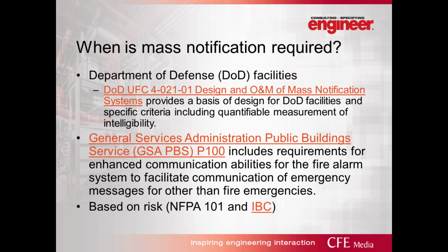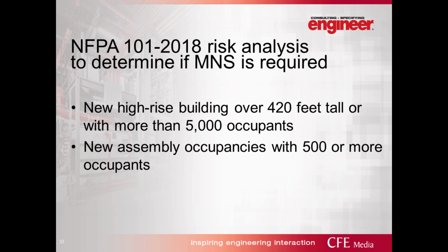I'm going to skip to mass notification. When's it required? The Department of Defense is the only organization that actually, at this point, mandates a mass notification system, and they have a standard in the UFCs. It's DOD UFC 4021-01, which provides the design guidelines for mass notification systems. Now, the General Service Administration in PBS P100 does include requirements for the fire alarm system to provide enhanced communication, but it doesn't go as far as mandating a mass notification system at this point.